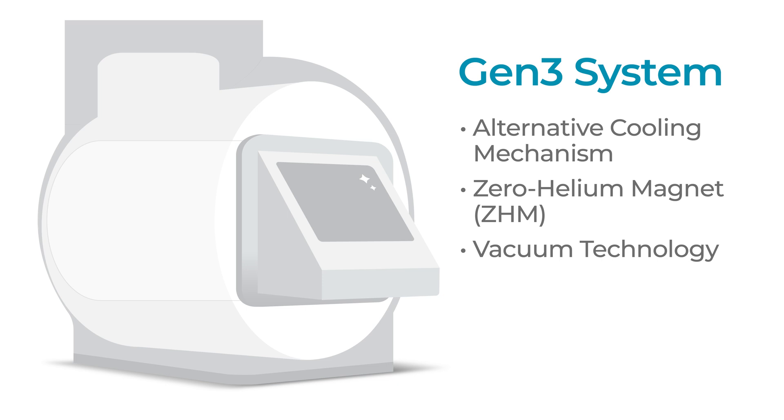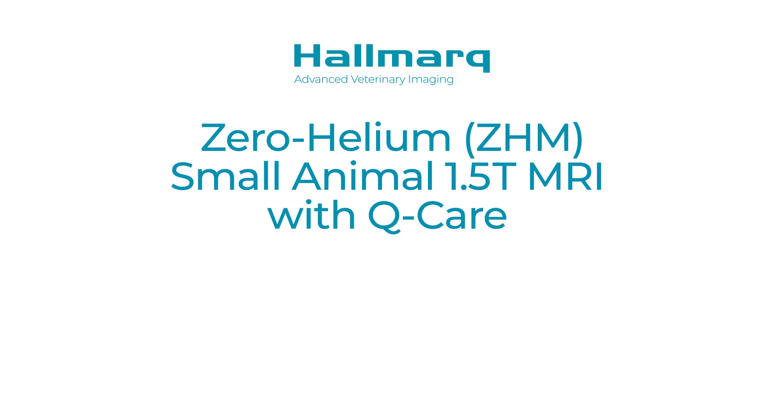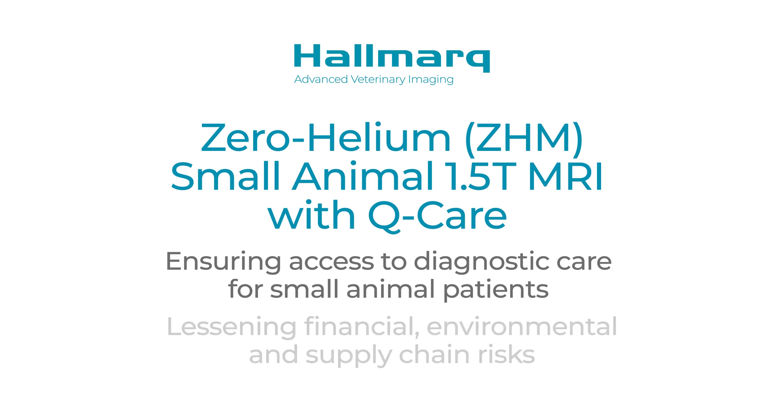It uses vacuum technology and a conduction-based cooling system that does not require helium, a quench pipe, or any additional power. This new technology, as well as the services provided by Hallmarq's exclusive Q-Care program, help to ensure access to diagnostic care of small animal patients while lessening the financial, environmental, and supply chain risks associated with traditional helium-based MRI systems.